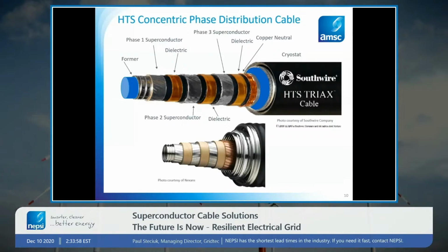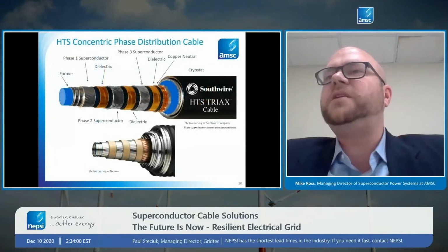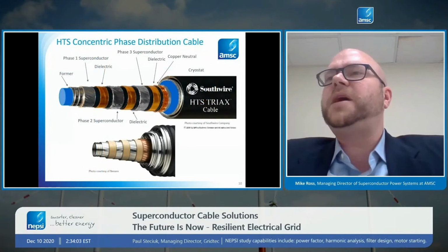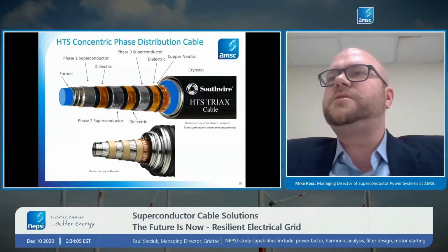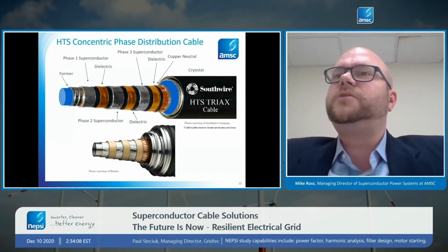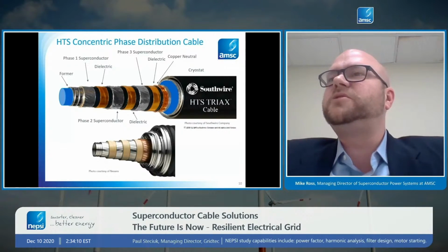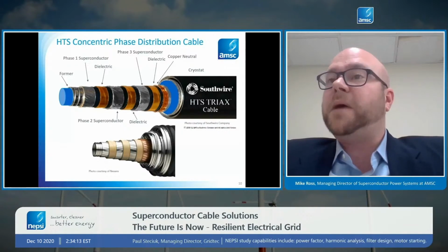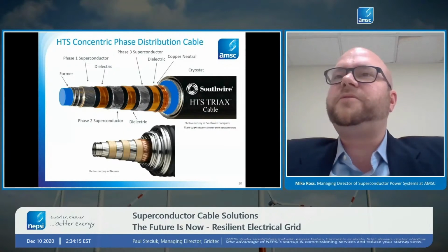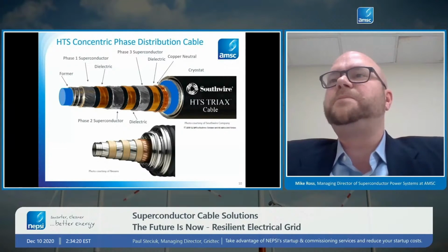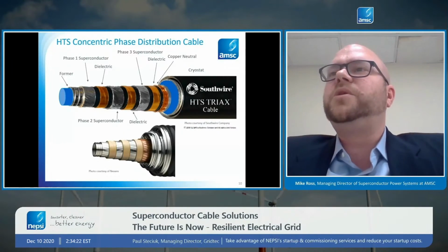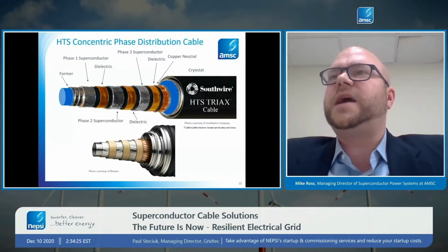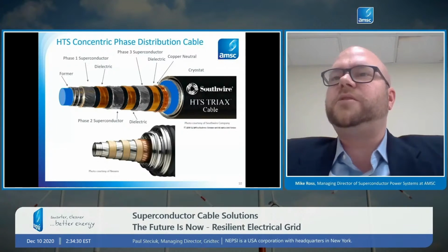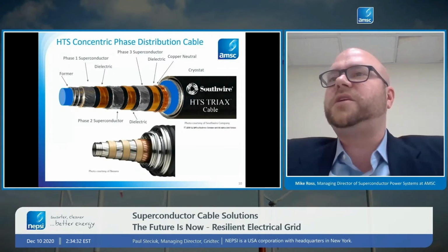And those 12 cables can't be right next to each other. They have to be spaced out by several feet. So you can imagine that a conventional cable system to move the same amount of current that this cable system can carry would be in a duct bank that would be 2 by 3 feet minimum, and in a lot of cases a lot larger. And we can replace all of that with a single cable that's about 10 inches in diameter. So that's the main advantage. Just giving you an idea of the main advantages of this technology.